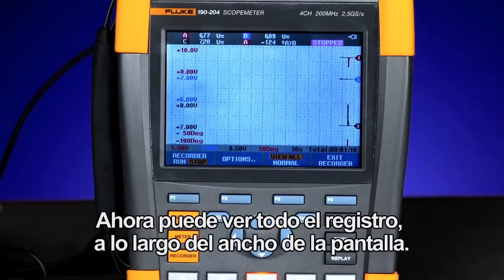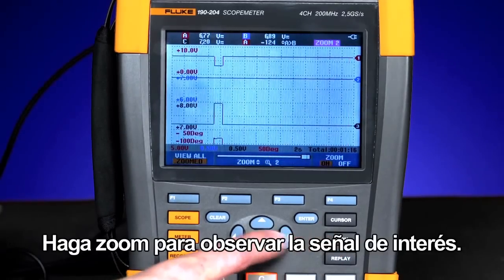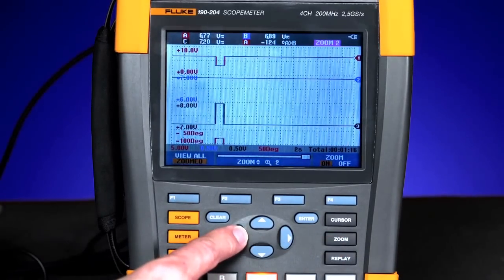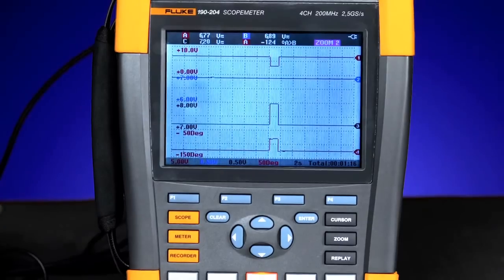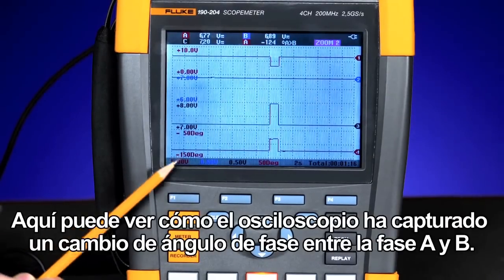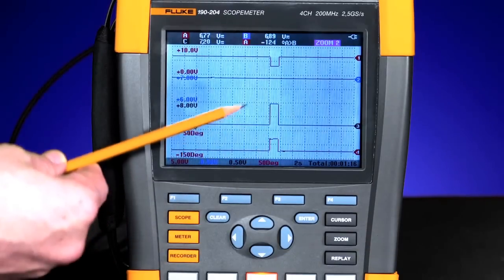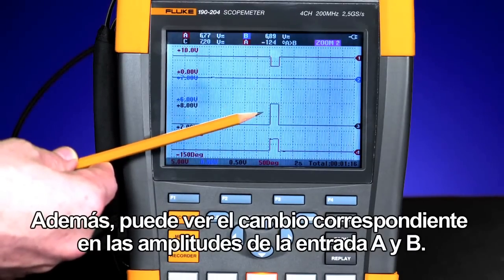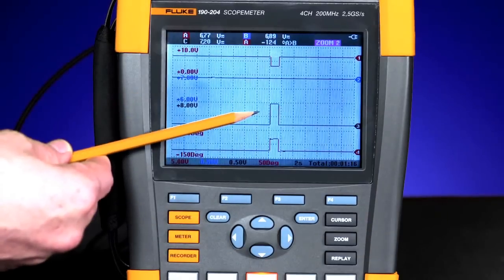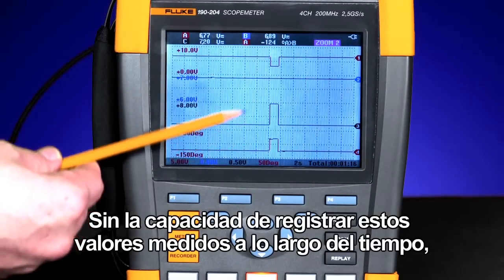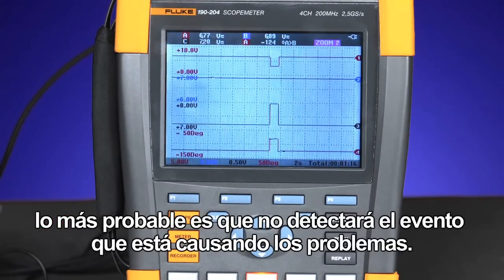Now you can look at the entire record across the width of the screen. Zoom in to look for the signal of interest. Here you can see how the oscilloscope has captured a phase angle change between phase A and B, and you can see the corresponding change in the amplitudes of input A and B. Without the ability to record those measured values over time, you would most likely miss the event that could be causing your problems.